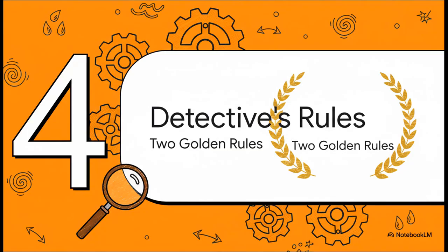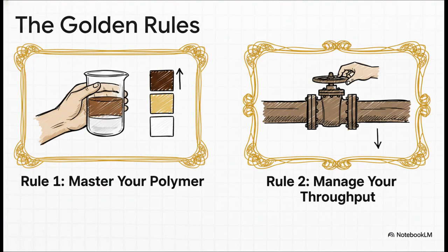Whew, we've gathered a lot of clues for both the belt press and the centrifuge. So now, let's wrap this all up with the two golden rules for any dewatering investigation. These apply to pretty much any machine you're running. Rule number one is simple. Master your polymer. As we've seen, the color of your water, your filtrate or centrate, is the single most powerful clue you have. If you can get that polymer dose just right, you've solved half your problems before you even have to touch the machine.